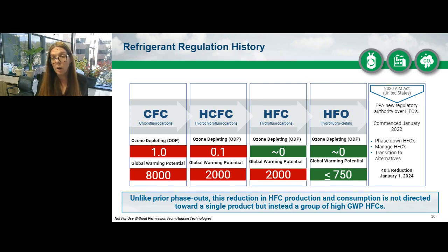And so from that point on, those refrigerants are only available through reclamation. There's a small tail of virgin production of 123 still left, but that's tailing off quite quickly, and virgin 123 will be phased out here very shortly as well.